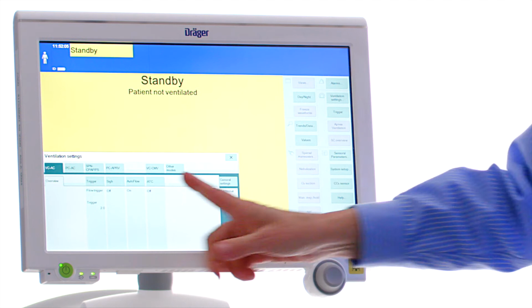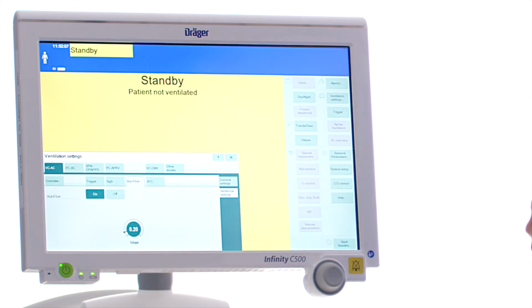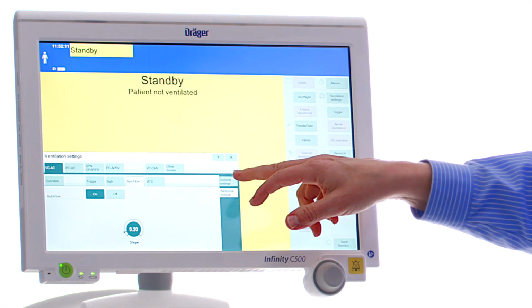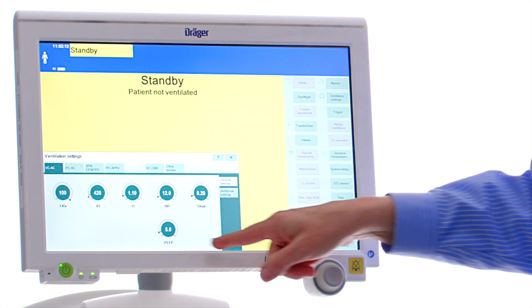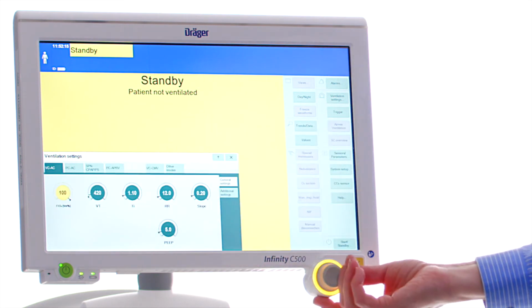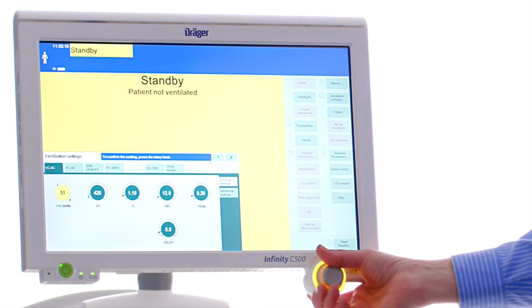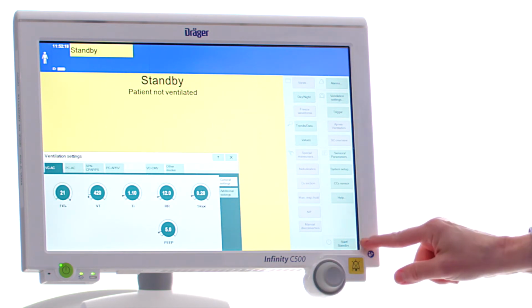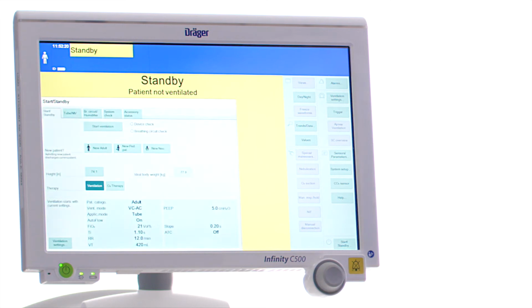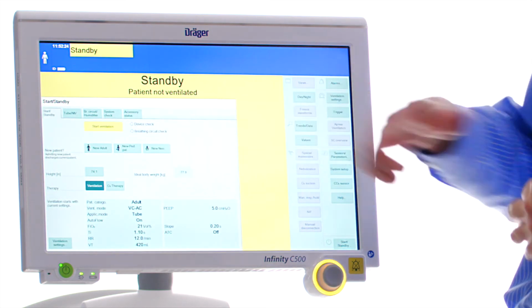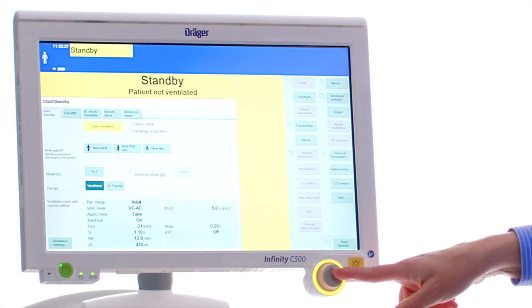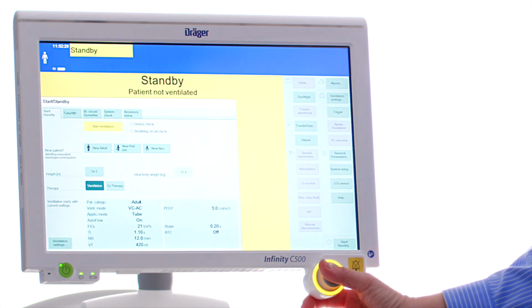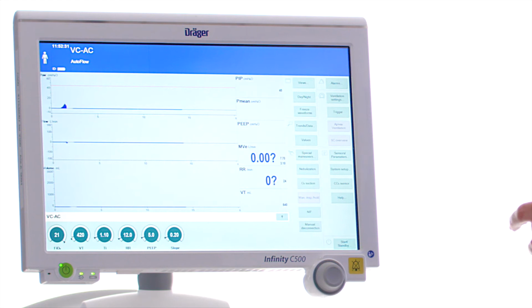Additional settings is where you will find auto flow, which gives you that hybrid volume-targeted pressure control breath. Once your parameters are set, again using touch, turn, confirm, we can go back to start standby when we're ready to begin ventilating our patient. Touch the start ventilation bar, which will light up the rotary knob to remind the user to confirm by pressing, and we're now ventilating our patient.